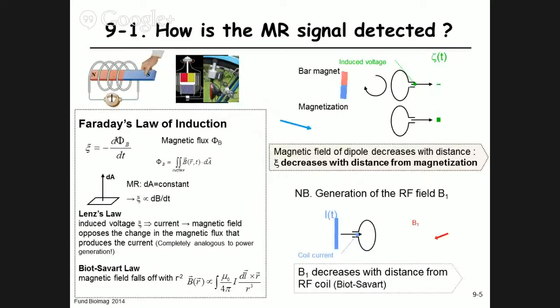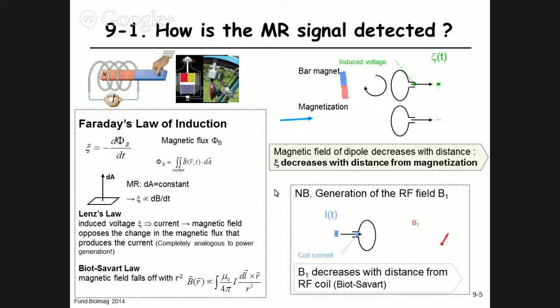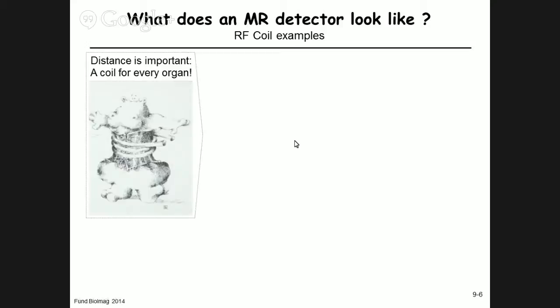The B1 field decreases with distance from the RF coil, whether for detection or excitation. So what does an MR detector look like? Since distance is critical, the key principle is: we have a dedicated coil for every organ. Ideally, a physicist would design an MR machine by squeezing the object into the coil to maximize signal. The physician says that's not patient-friendly, so a compromise must be found.